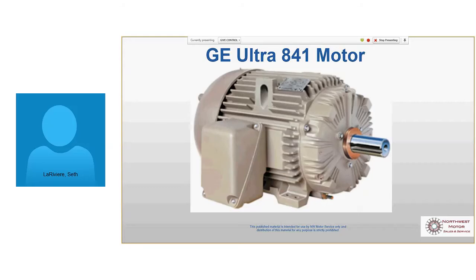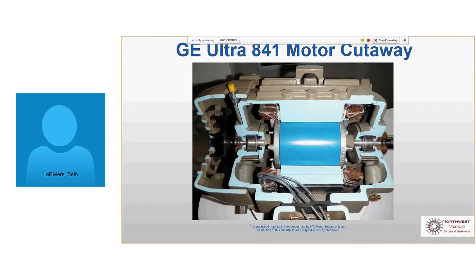On the inside, there's a couple of features that really make this motor so rugged, and it's the reason it lasts so long in industry. The first thing is, this is an oversized bearing on the drive end, so it's one size larger than NEMA requires. And on the back end, they put the same size bearing here that they put here. That's uncommon. Most guys put a smaller bearing back here, because this one carries all the load, particularly in a belt drive, right? So this is going to get all the radial load.